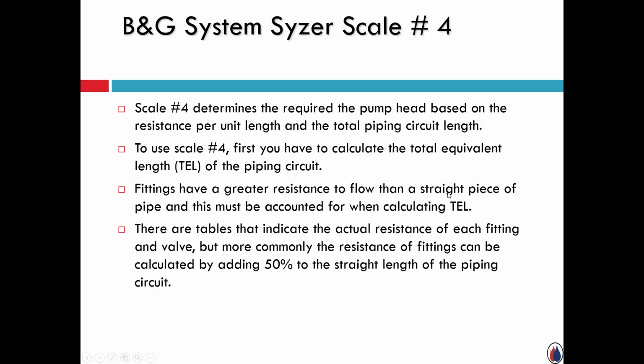Out in the field, to be quite honest with you guys, if you're engineering and designing, you're responsible from the very beginning, you're going to be a lot more accurate. What they're talking about here is a rule of thumb. Sometimes when you're out in the field and you're trying to help a guy, maybe either size, resize, there's been an addition added, whatever the case may be, but you can't find all the pipe. It's existing. Some of it's behind the walls. So you kind of do what they call a swag method. And that's a scientific wild ass guess.